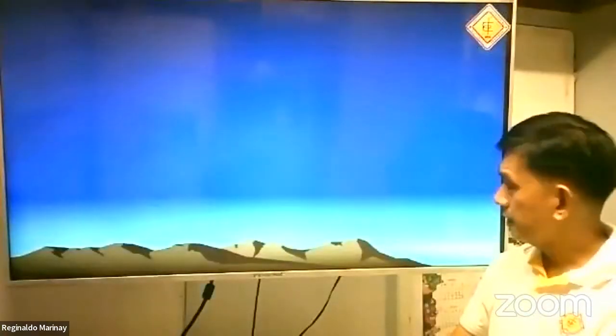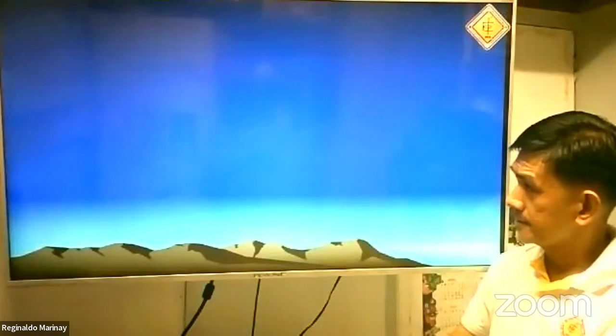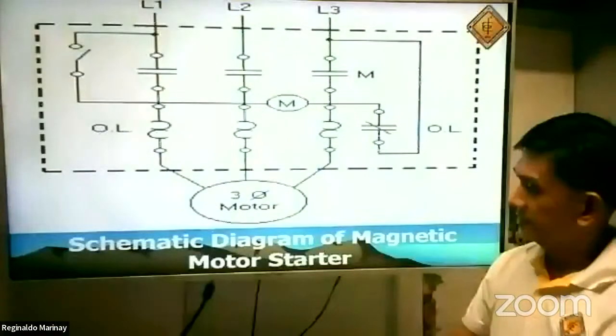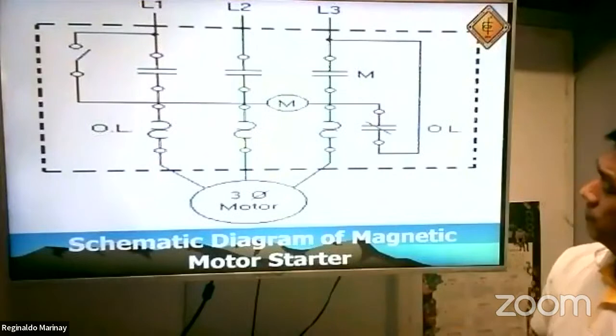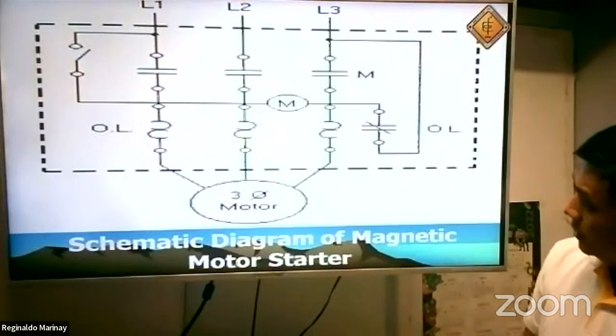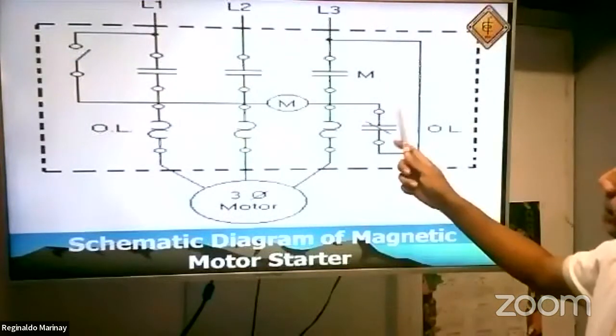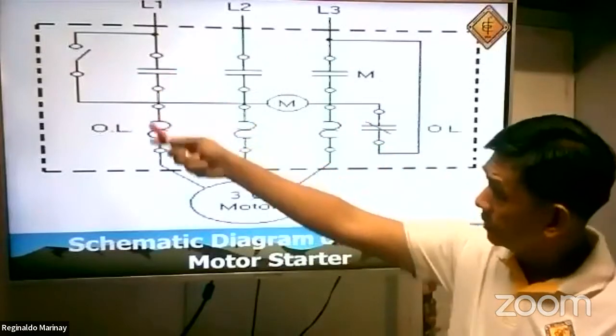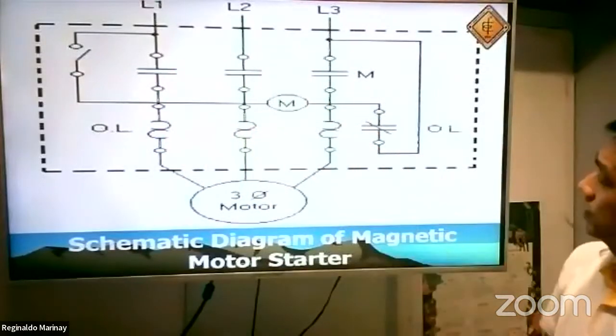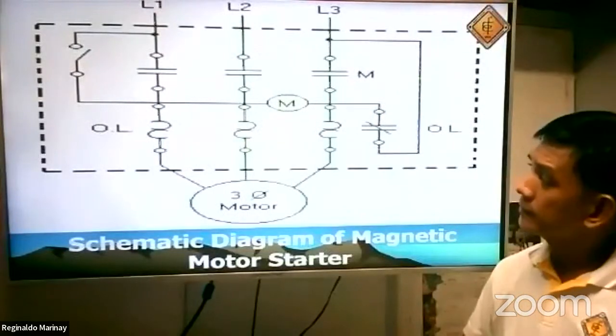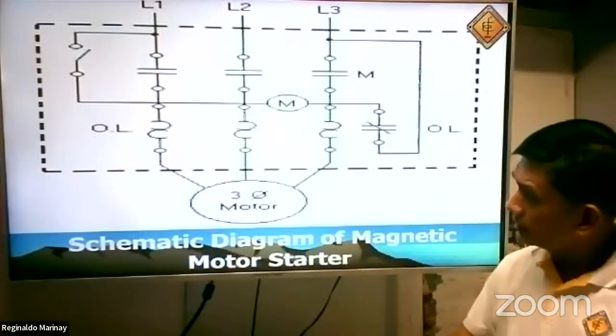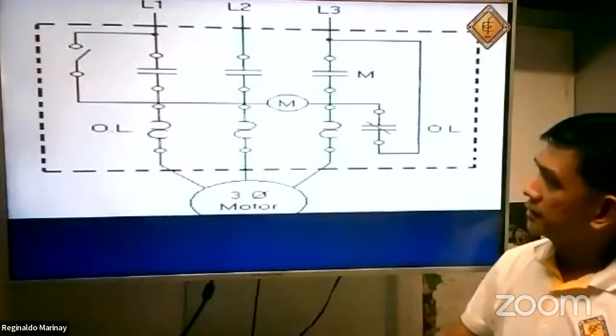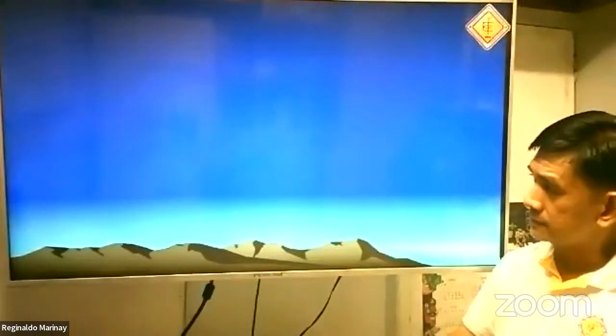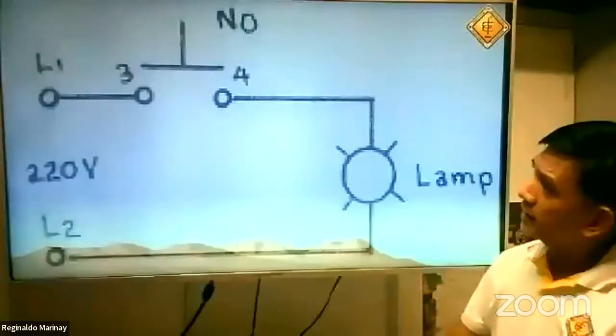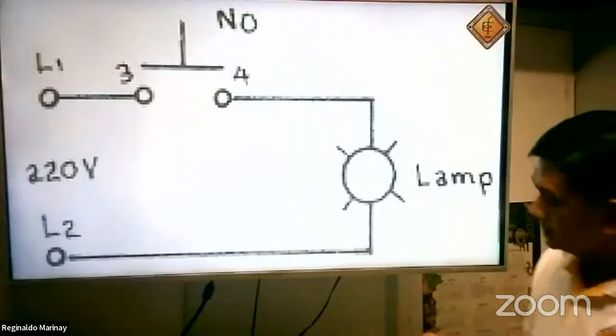We have the schematic diagram. Take a look here. Schematic diagram of magnetic motor starter. You see this one? There is a magnetic contactor. There is an overload relay already in the magnetic motor starter. It's actually a combination of contactor and overload relay inside of it. Let's have some wiring exercises, basic exercises.